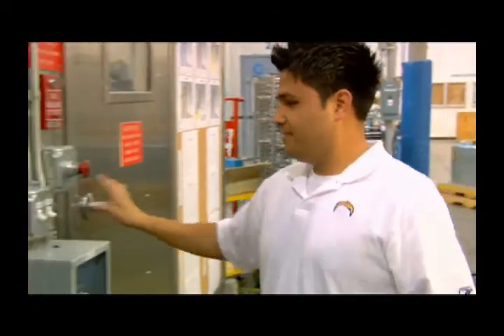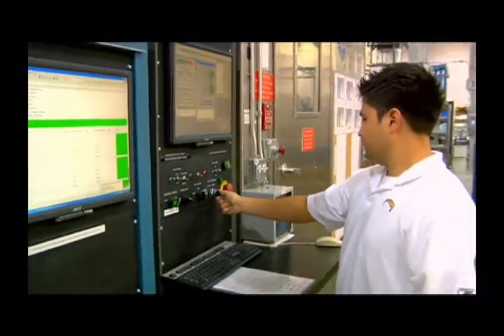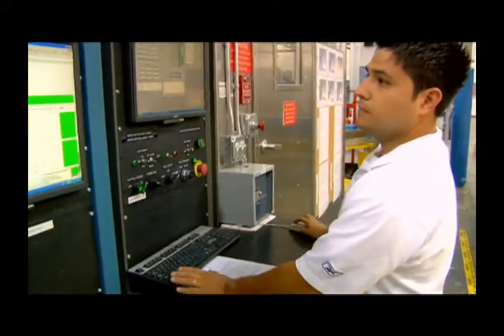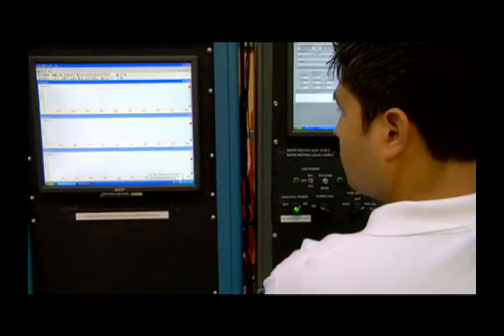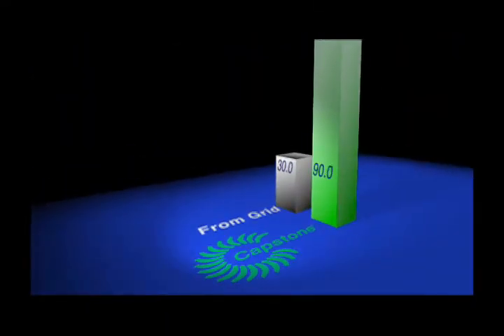The benefit of a microturbine to a business is we can provide electricity cheaper than they can buy it from the grid. So we can use commercial fuels like natural gas to fire the turbine and produce electricity cheaper than we can do with the grid. What's even better is we can take the heat off the machine to offset the boiler loads or the building loads that they currently have, as well as air conditioning loads if we use an absorption chiller. So we go from 30% efficiency, which is similar to the grid, to 85 to 90% efficiency, which is much, much higher. So your economic payback for the project can be as low as 3 years, as long as probably 7 years. But in addition, you have cleaner power, lower carbon footprint, and you've got long-term economic benefit of producing your own power, heat, and cooling.